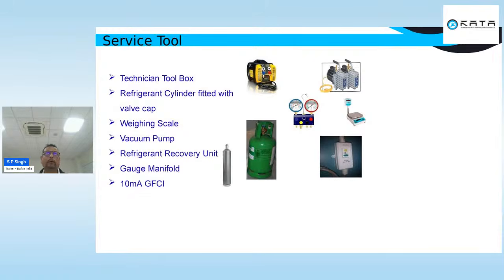If we carry out an inspection, you will find that most of the charging pipes are cracked. When we are recovering the refrigerant, or pumping down the system, there is a very likely chance that air will enter, because when you pump down the system you are creating a vacuum in the system. When the vacuum is done and you are recovering at a positive condition, atmospheric air will immediately enter the system, and it will give you problems. Even the compressor can get damaged, or even burst. That is the reason our tools should be proper, especially the charging pipe, and we should have a charging valve, so that less refrigerant is leaked out from the system.